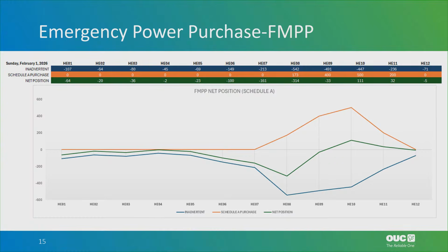With the energy emergency alert declaration, the pool was able to procure emergency replacement power from other utilities in the Florida Reliability Coordinating Council. The market was frozen; there were no transactions to be had within those morning hours, but the emergency declaration allows other utilities to sell non-firm emergency replacement power as long as they have it. Those non-firm sales can be clawed back if the utility experiences a unit trip and can no longer provide that emergency assistance. In that event, the load shed would have progressed. We're very fortunate that emergency power was available from other utilities.